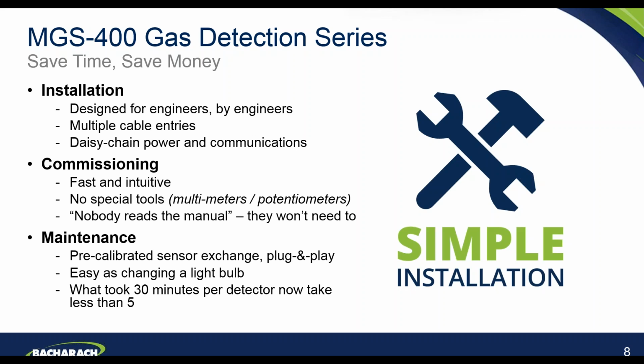In terms of the maintenance aspects, a key step forward for ourselves, and certainly compared to many parts of the market, is that the 400 series offers fully pre-calibrated sensor exchange, which is a simple plug and play. It's as easy as changing a light bulb. You essentially unscrew the old sensor module, screw the new sensor module in, and it's very quick and simple and easy. So what would have previously taken perhaps 30 minutes or so per detector to carry out a calibration process can now be done in less than 5, with no specialist tools required, no calibration gas required. It's a very quick and easy and pain-free exercise.